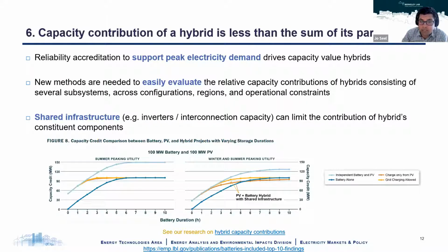The light blue line now shows the combined capacity credit of both a standalone battery and a standalone solar project, each with 100 megawatt capacity. But when infrastructure such as inverters or interconnection capacity at the point of interconnection is shared between both resources, it can limit the total available capacity, in our example, again, at 100 megawatt, and thus leave about 30 to 50 megawatts of capacity inaccessible.